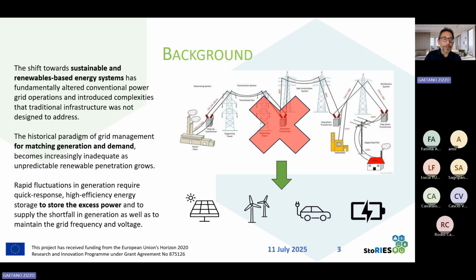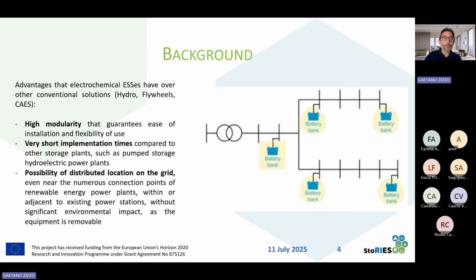Energy storage systems can be used to store the excess power from the unpredictable generation and to supply the shortfall in generation for maintaining the grid frequency, that is the most important feature of the grid, because without a stable grid frequency, we have an unstable grid, we have system split, we have blackouts and so on. But also energy storage systems can be used for restoring voltages, for maintaining the voltage in the different nodes of the grid in the ranges that are allowed by the distribution system operators or transmission system operators.